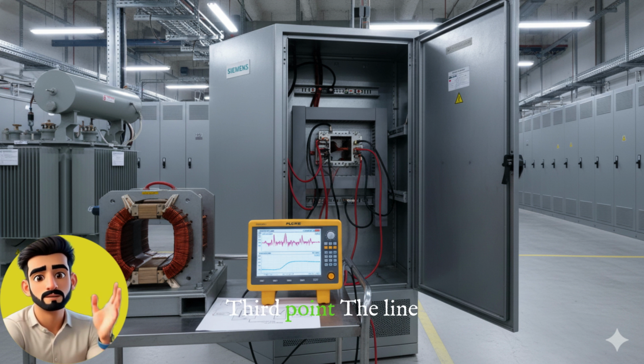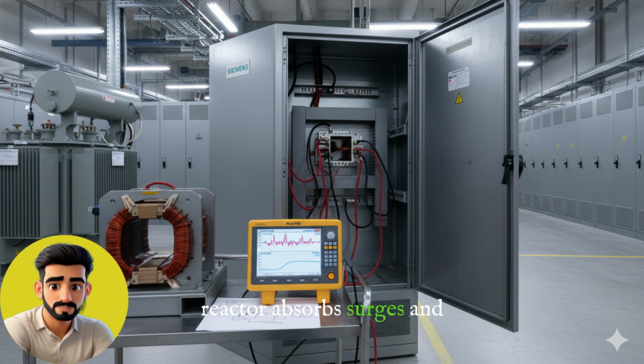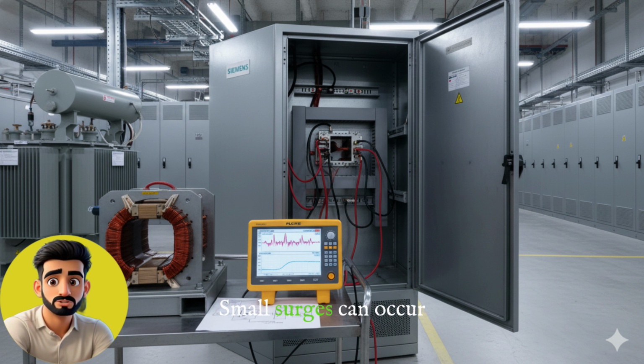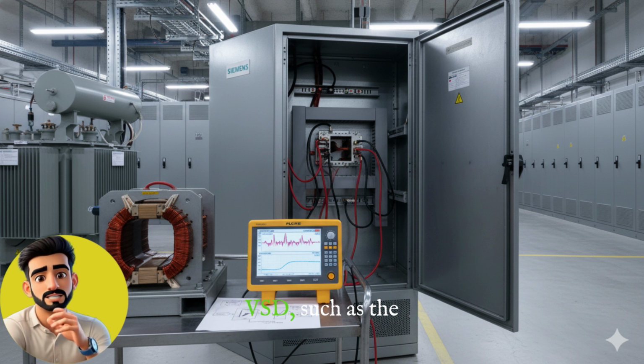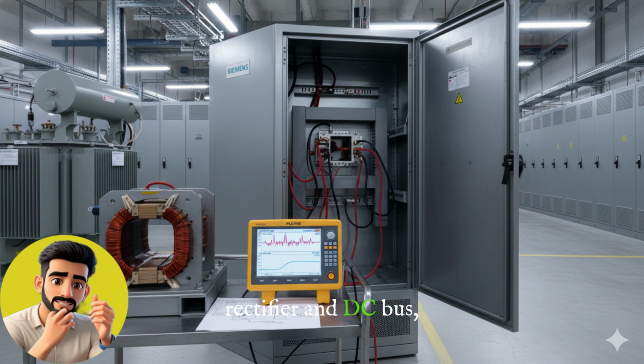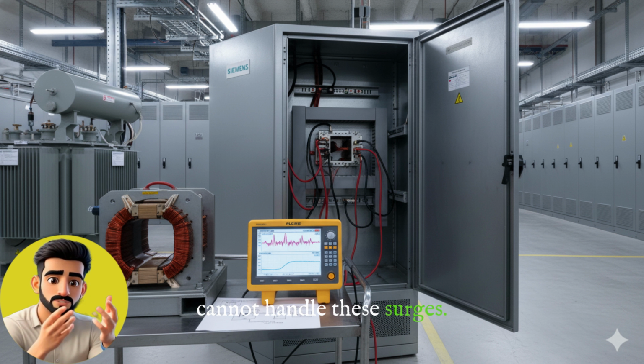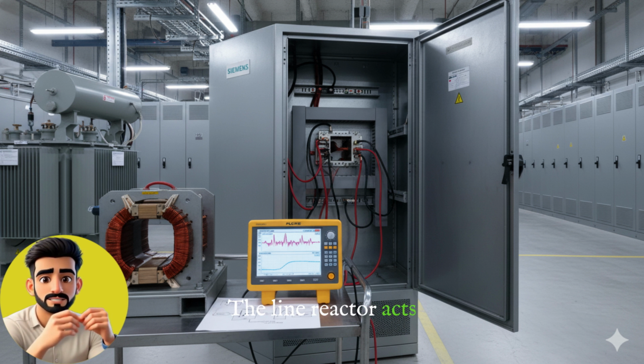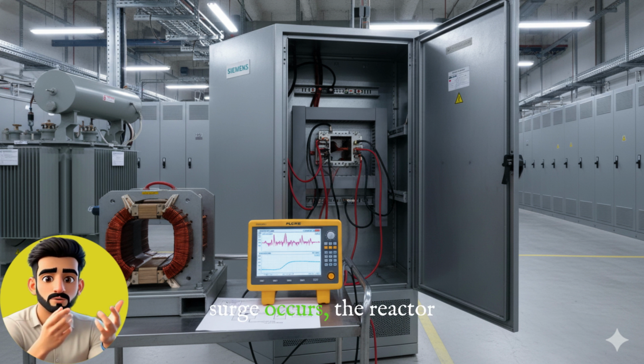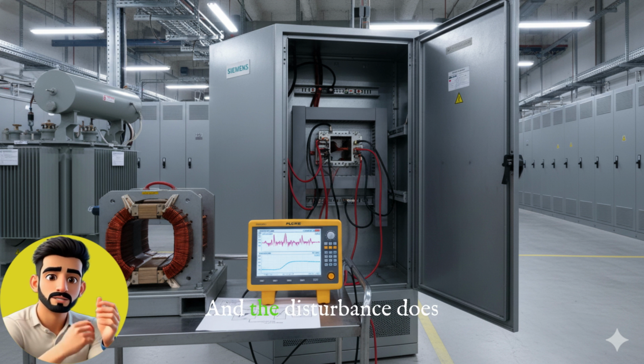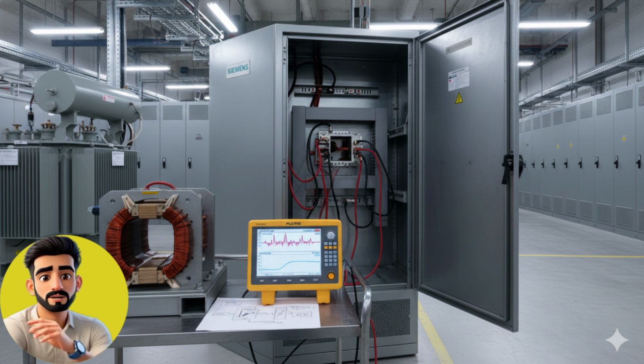Third point. The line reactor absorbs surges and transients. Small surges can occur in the grid at any time. Sensitive components of the VSD, such as the rectifier and DC bus, cannot handle these surges. The line reactor acts as a shield. As soon as a surge occurs, the reactor absorbs it, and the disturbance does not reach inside the VSD.